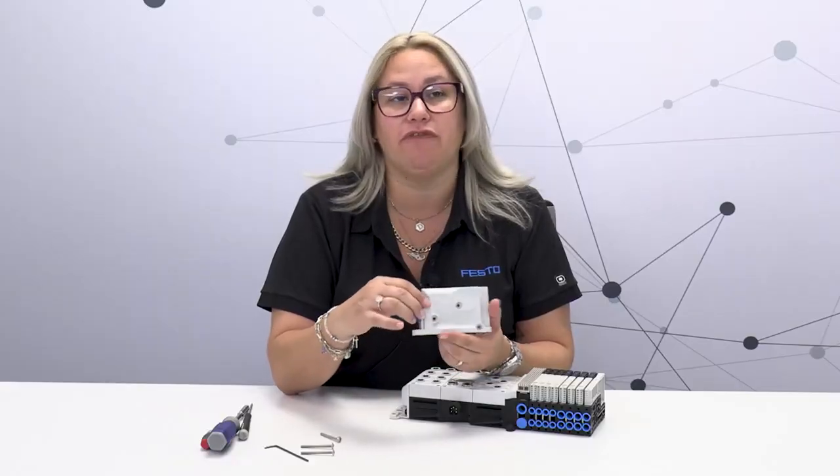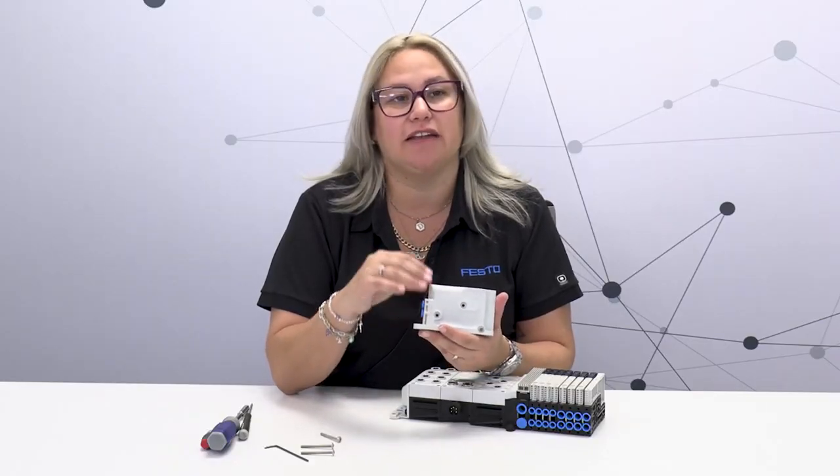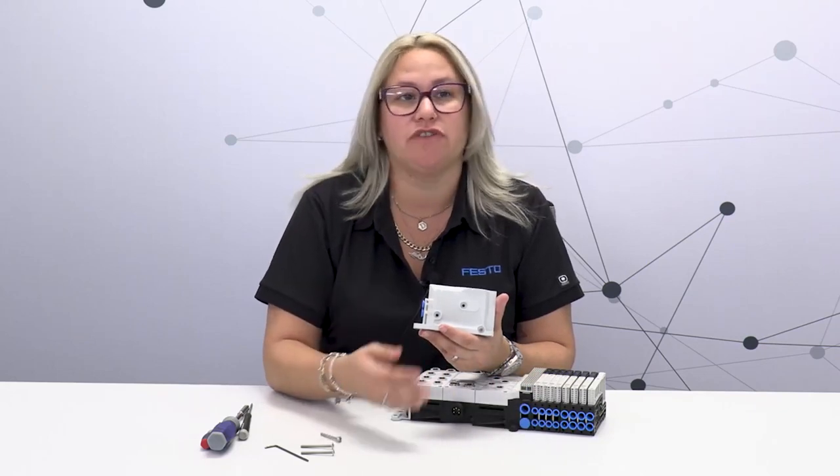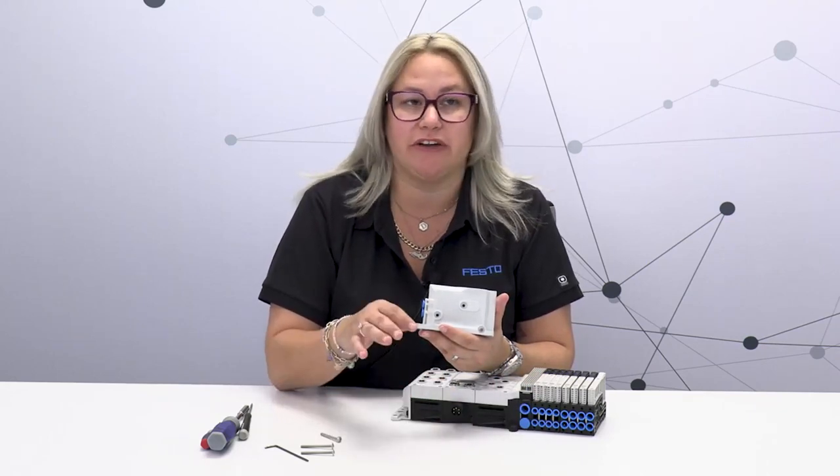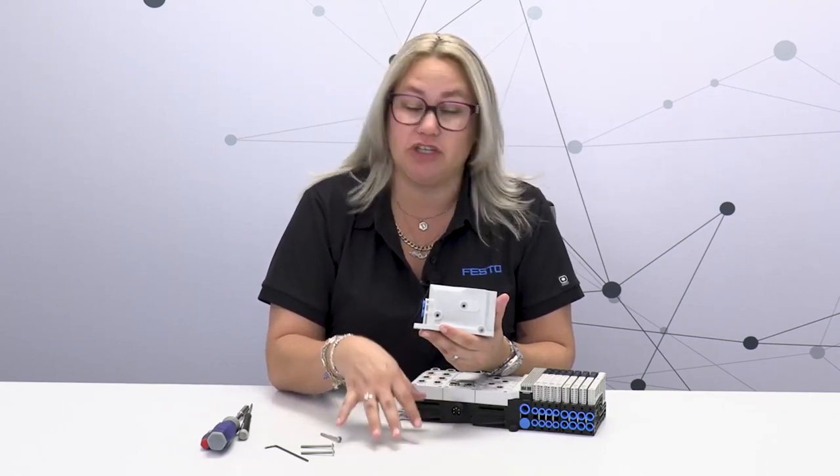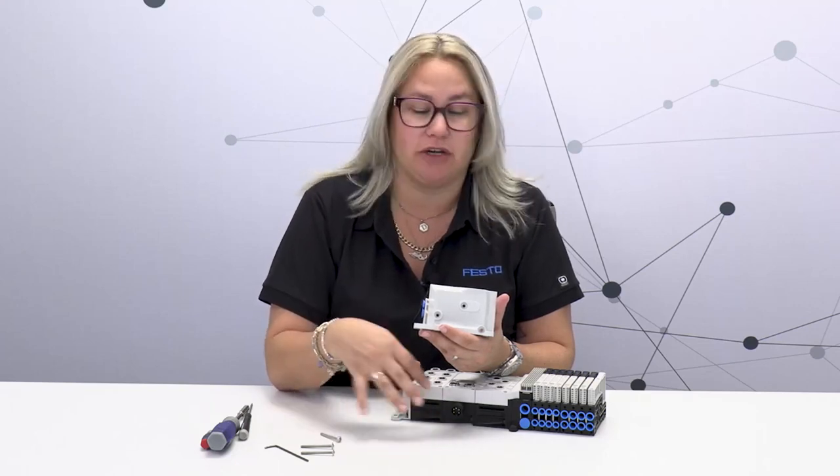One of the nice features about all Festo valve manifolds is that the pilot is actually controlled from the manifold sub base, not from the valve. That means that if you ever want to change from internal pilot to external pilot, it's very easy to do in each manifold by just simply changing a few parts.